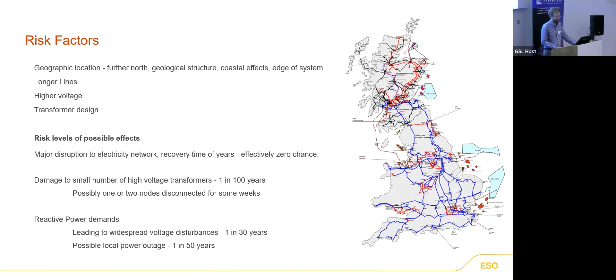Reactive power demands: in a 1 in 30-year event we could see widespread voltage disturbances across the network, and in a 1 in 50-year event, possibly local power outages. But again, there wouldn't be any permanent damage - it would be a matter of returning those demand points in maybe a matter of minutes, or maybe a bit longer than that.